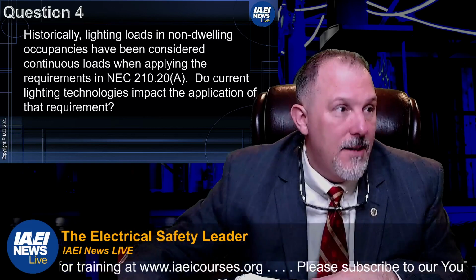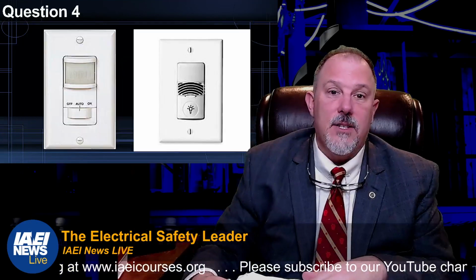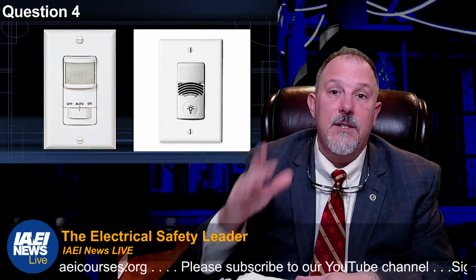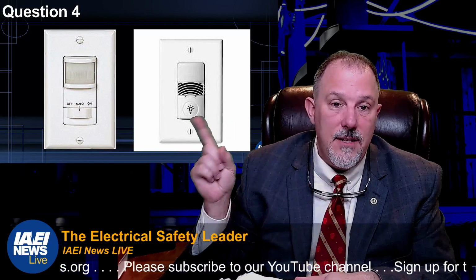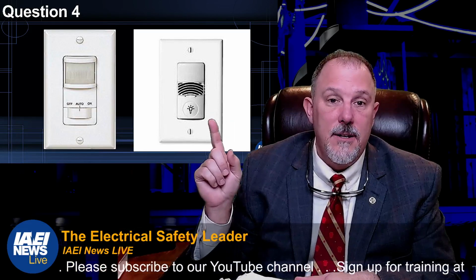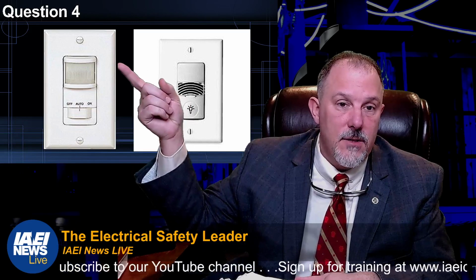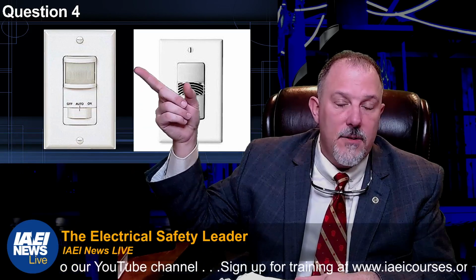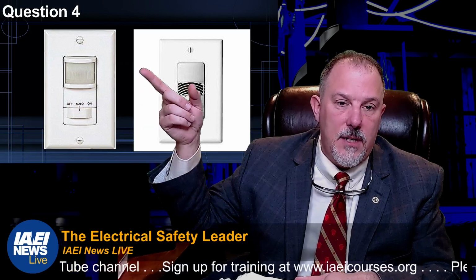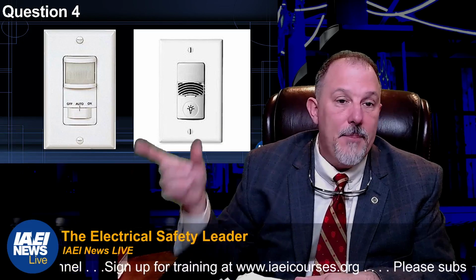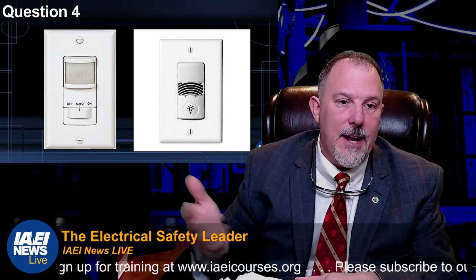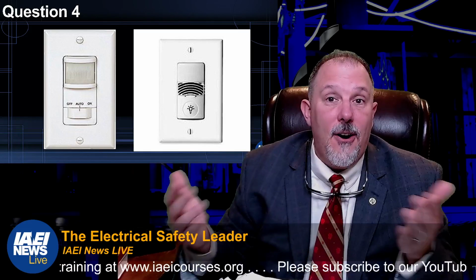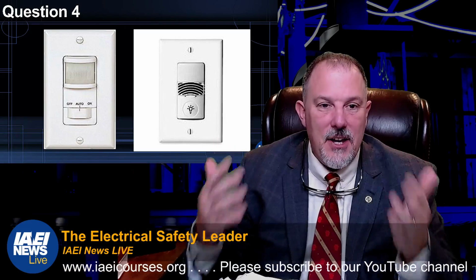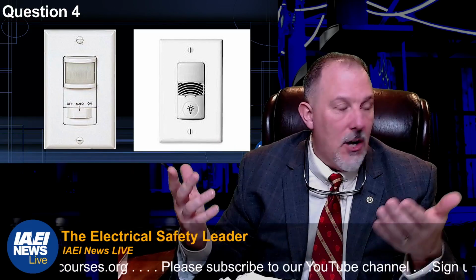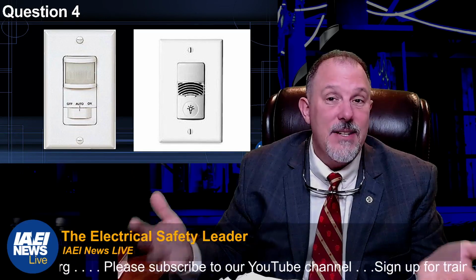And it's not this guy's opinion. It's not anybody else's opinion. It is between you and the AHJ. These technologies exist. These are sensors, right? That sensor up there detects the occupancy within that room. But look, I can turn it on and I can turn it off and I can put it in auto. So it has the option to be on. And if I leave it on for more than 3 hours, it is a continuous load.